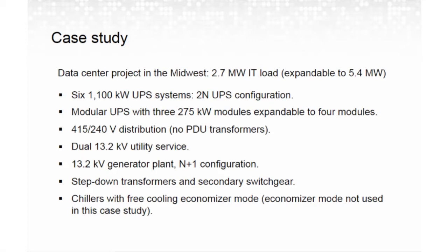They do have six 1100 kW UPS systems. They're in a 2N UPS configuration, so an A and B, three on each side. The UPSs were modular, so there were three 275 kW modules, and the fourth was not provided day one, so it could be expanded to four modules in the future. We did use 415/240 volt distribution, so there are no step-down transformers. It goes straight from the UPS out to the cabinet. It has dual 13.2 kV utility service, and we also used 13.2 kV distribution from the gen plant.